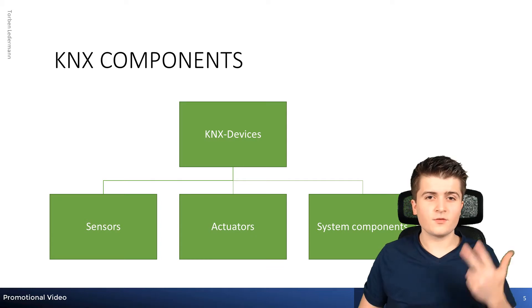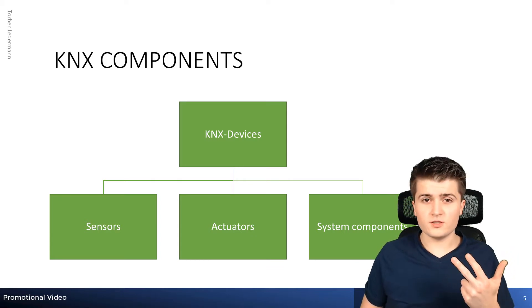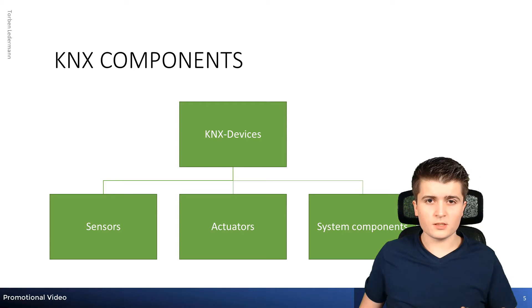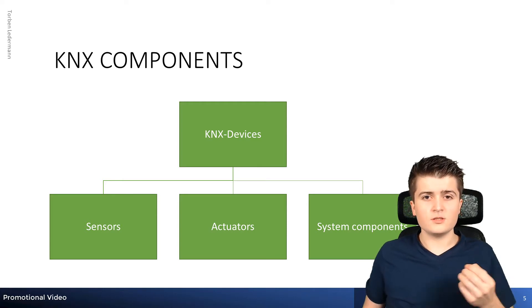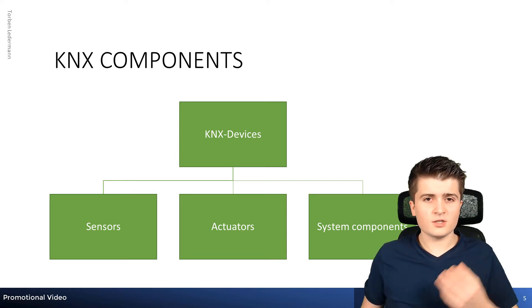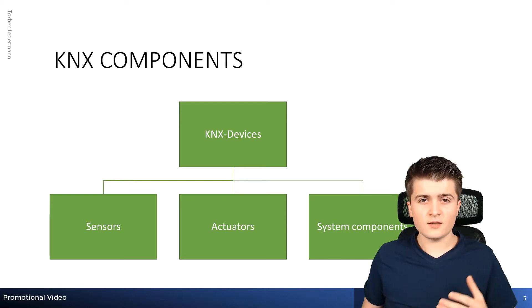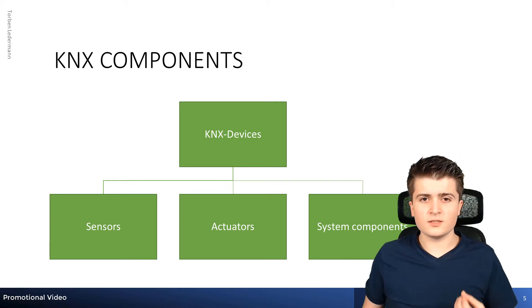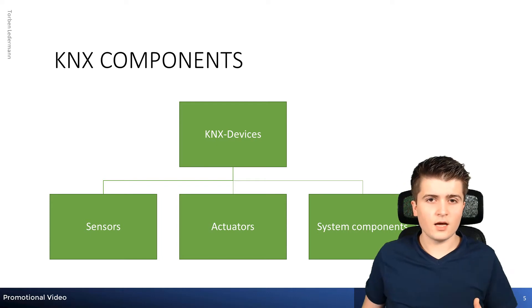KNX components can be divided into three larger groups. First of all there are the sensors, which convert physical information — like switching a push button or measuring temperature — into digital KNX telegrams. The complete opposite of a sensor are the actuators, which perform actions by converting the digital KNX telegram into a physical action like switching or dimming the light.